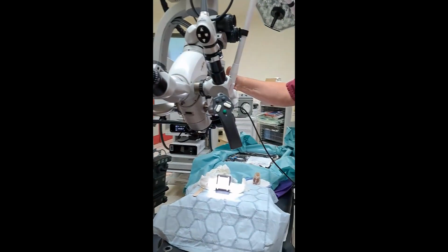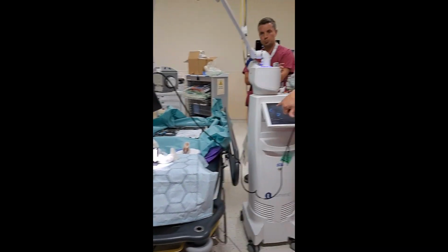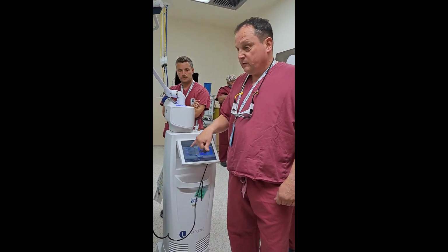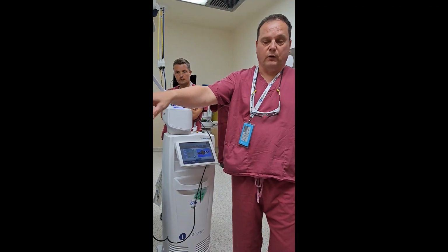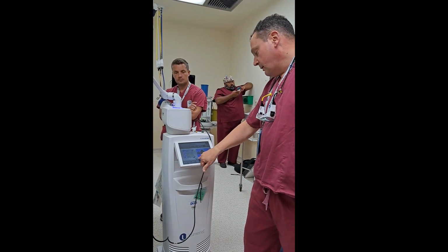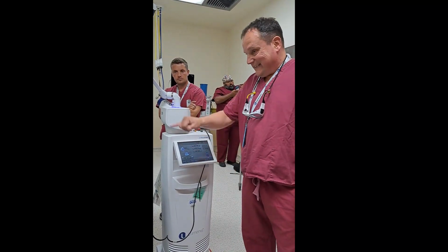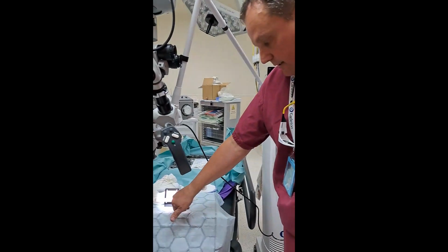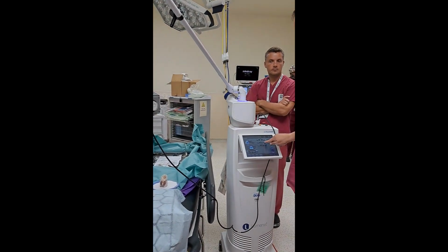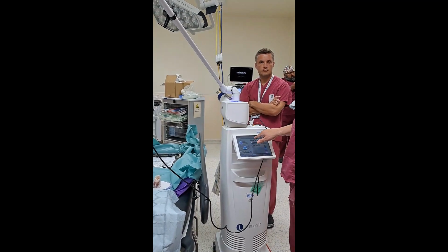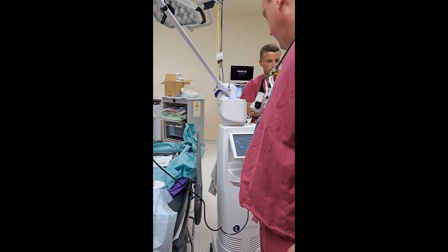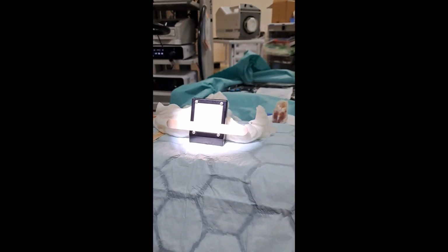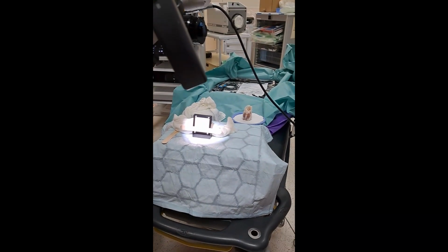What the scanner allows us to do is set up separate protocols on the machine with a scanner in place. So we say ENT, AcuBlade, 400 millimeters, which means generally we're working at 400 millimeters focal length, which they do for larynxes. And we set up a treatment protocol. What the scanner allows us to do is shapes. Mr. Ibrahim spoke about the circle earlier, which you can see there, and we can manipulate the size of the circle up to 5 millimeters. You can have a line, which you can manipulate up to 8 millimeters, and you can have a left or right crescent. I'll just elongate that so you can see what it does.